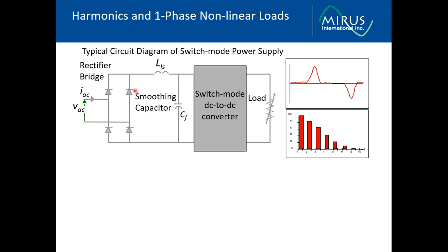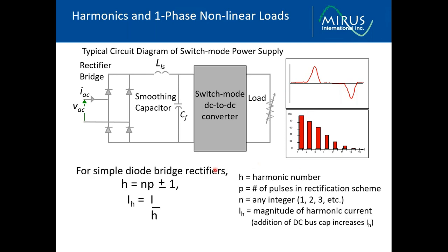So in a single phase application, the current being drawn is a single pulse. It contains much higher levels of harmonics. Again, if we follow this equation, it's a two-pulse scheme here, and the harmonics then, if you put P equals 2, you're going to see 3rd, 5th, 7th, 9th, and so on. So all the odd-order harmonics, the predominant ones being the 3rd and 5th.